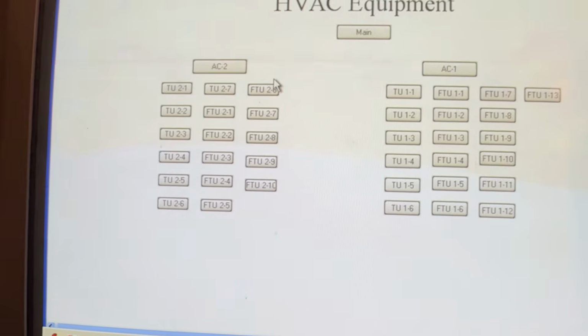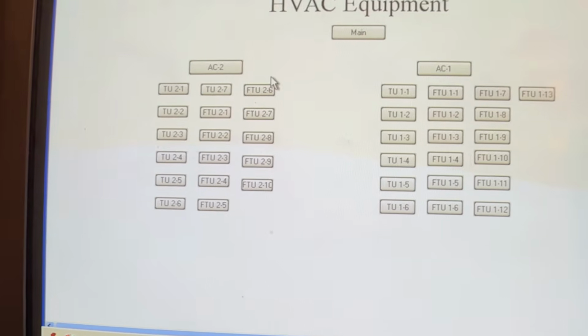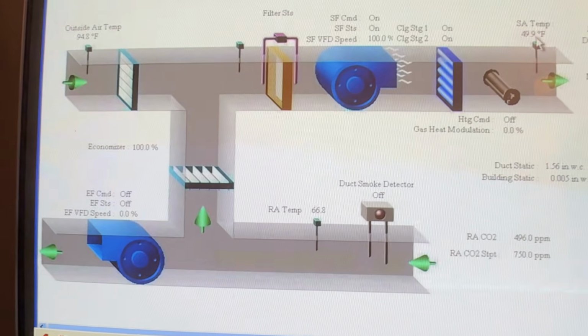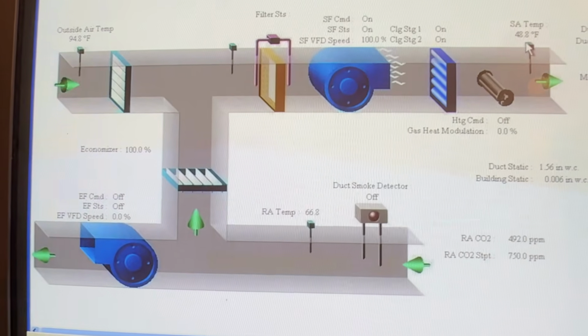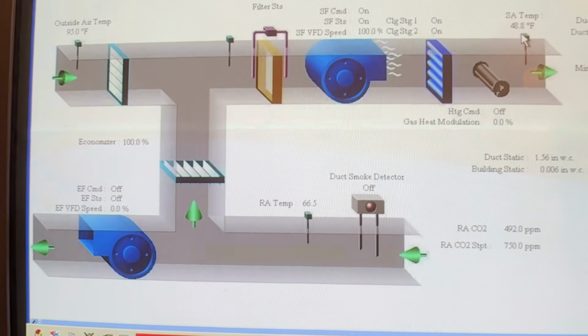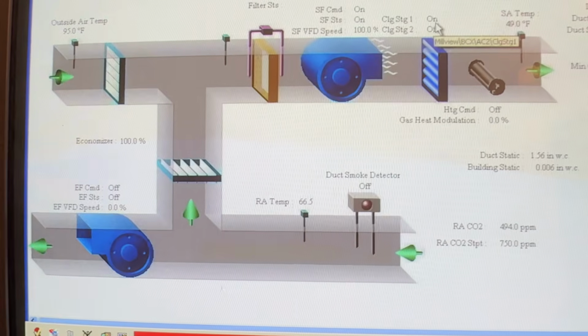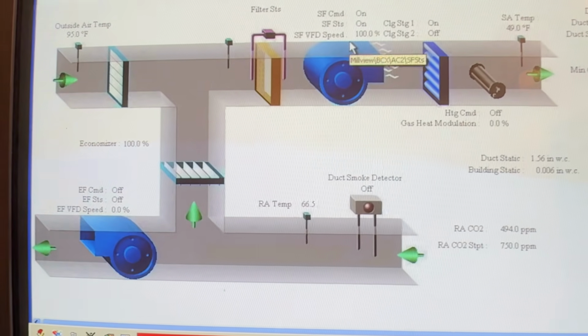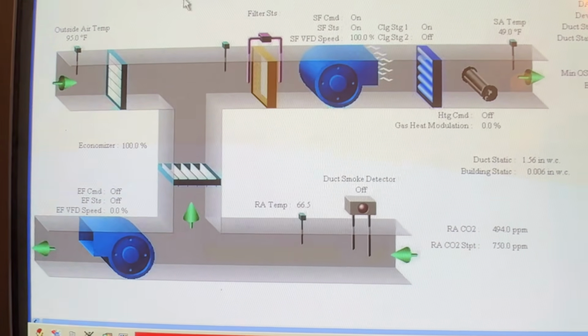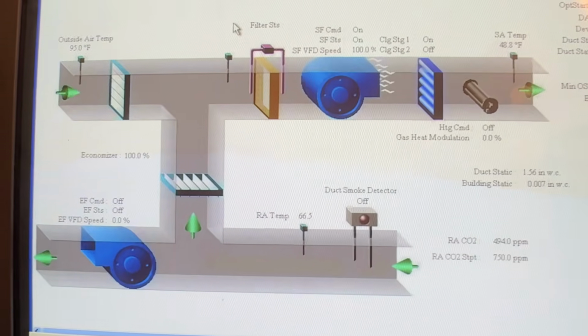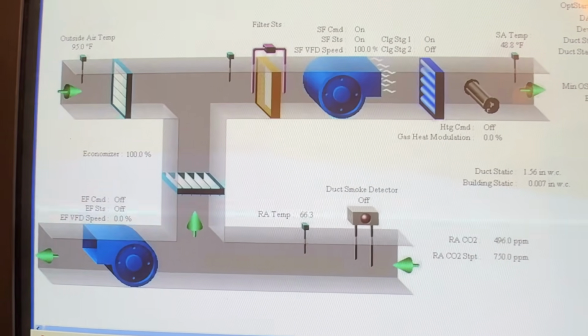AC1 is our second floor, AC2 is the first floor, and we can see here that the supply temp is currently at 48.8. Cool stage 1 is being called for, we're at 100% fan, so this one's working. And I've been inside, downstairs is definitely cool, upstairs is warm.